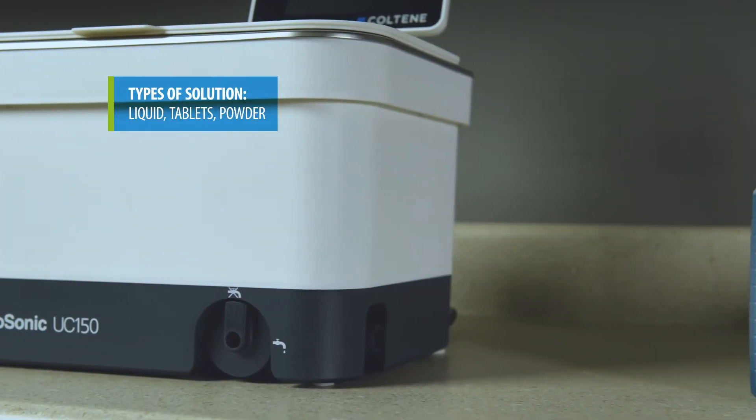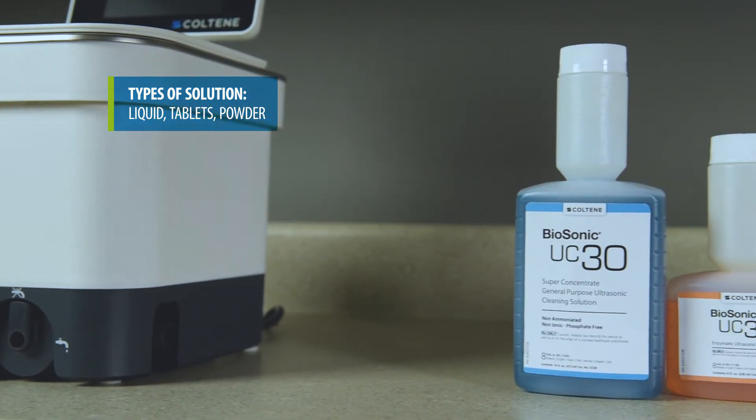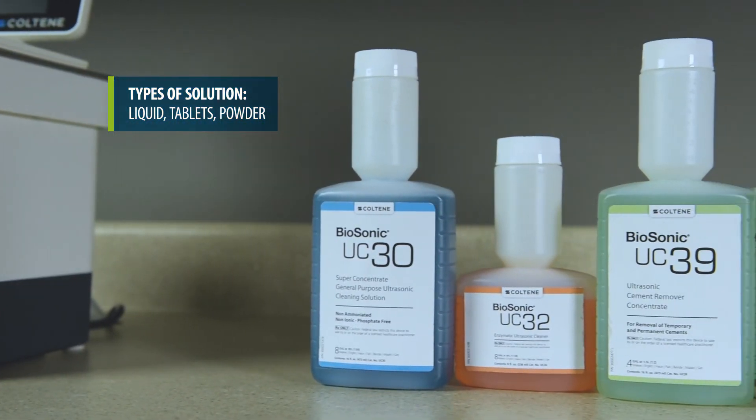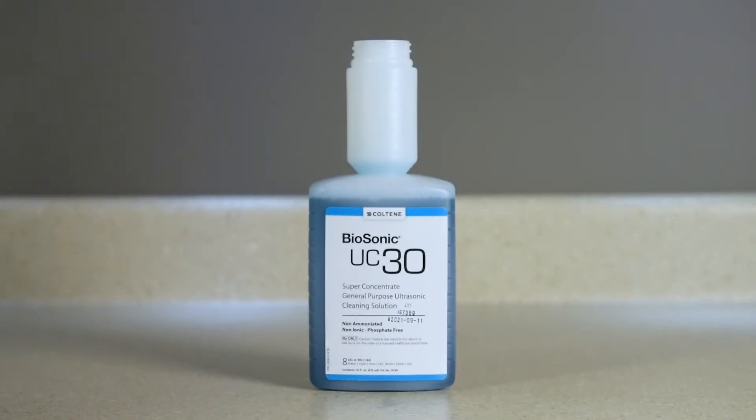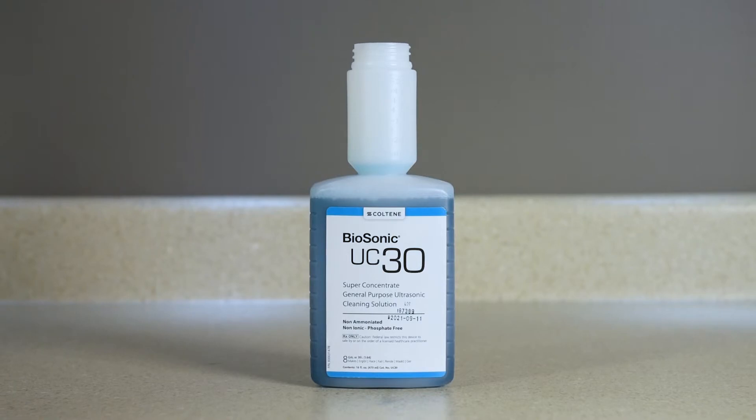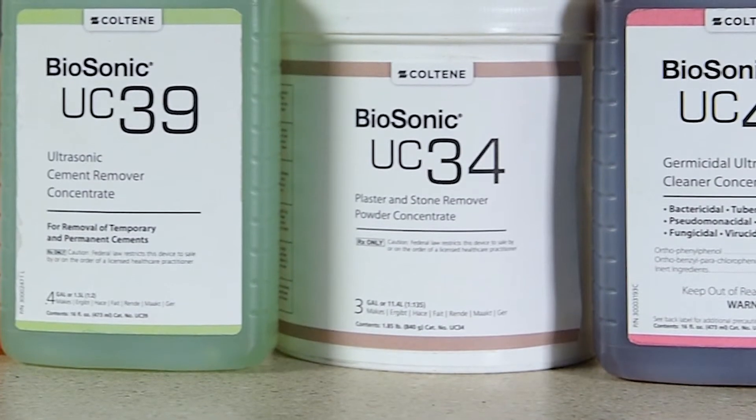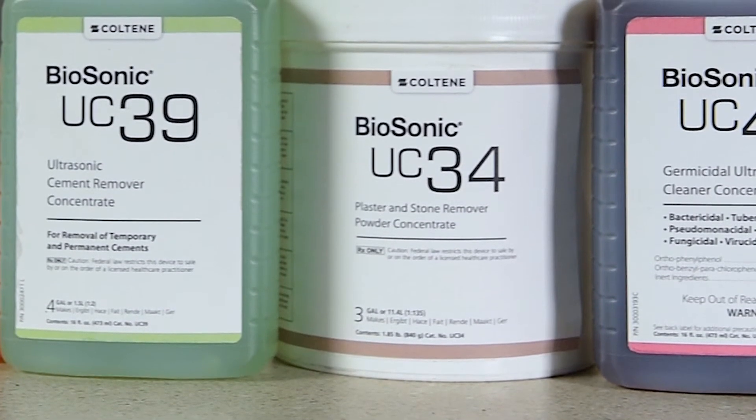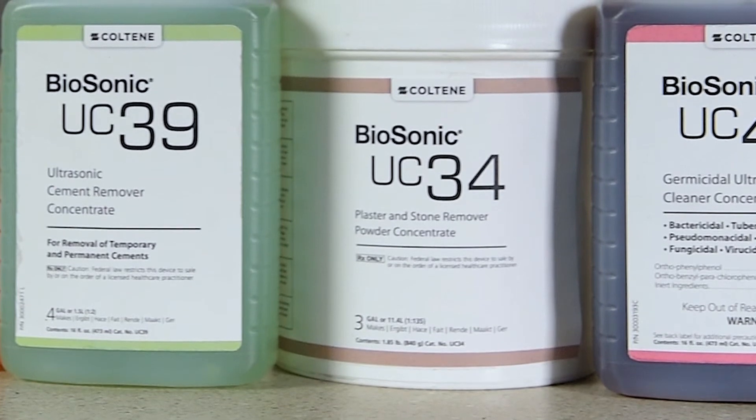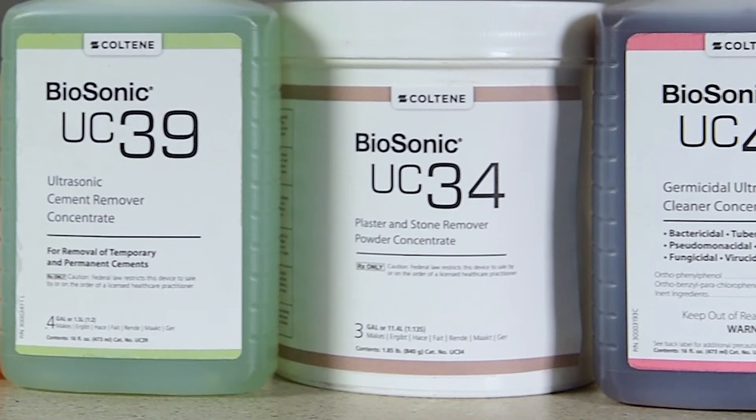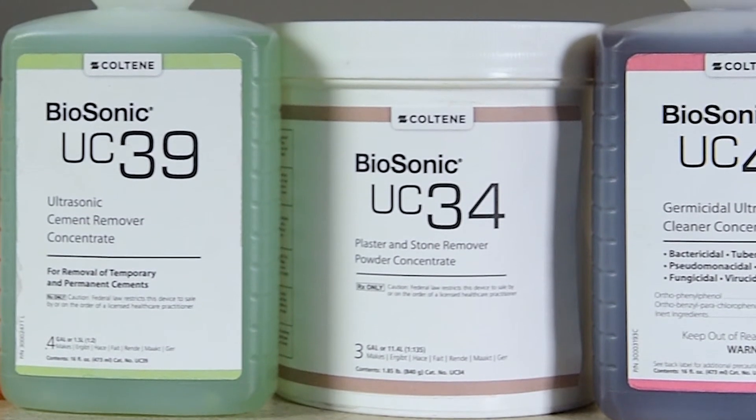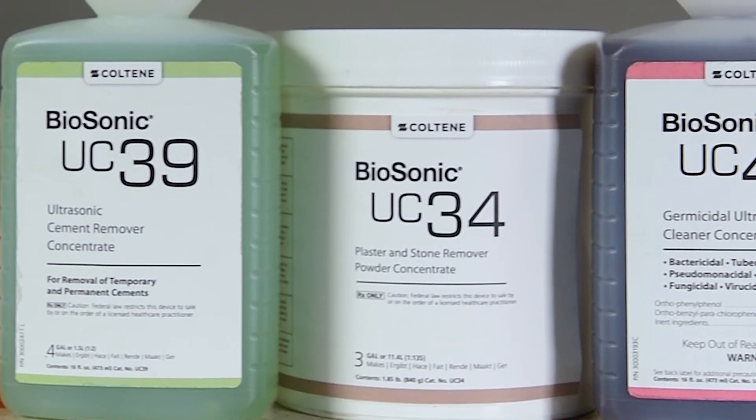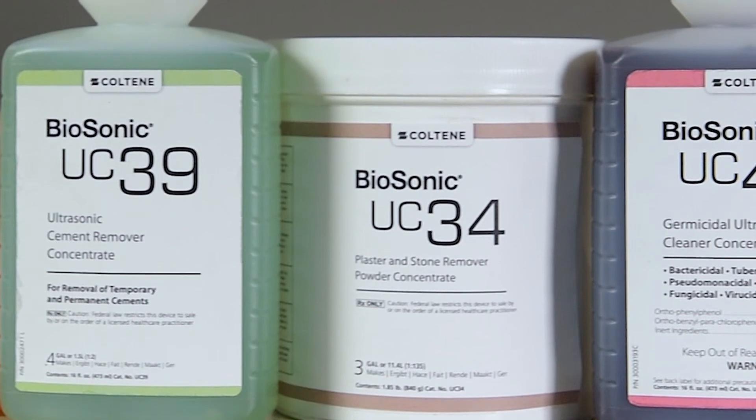Adding one of three types of cleaning solution reduces fluid surface tension and contains ingredients designed to optimize the ultrasonic cleaning process. Liquid solution allows for instantaneous solution preparation, while tablets and powder solutions must be fully dissolved prior to beginning the cleaning process. It is recommended that tablets and dry solutions be dissolved in hot water prior to placing them in the tank to prevent them from settling on the bottom of the tank until the ultrasonic action dissolves them.